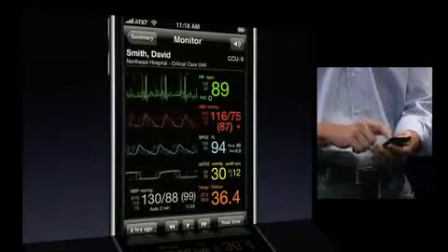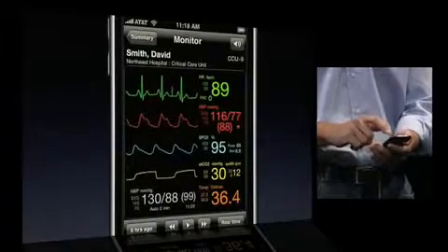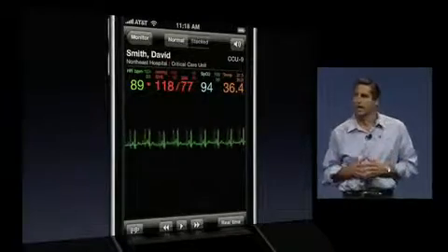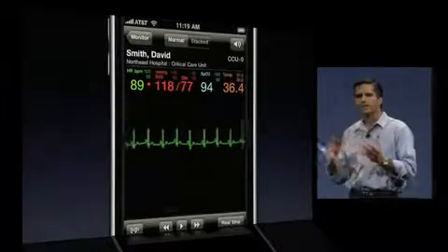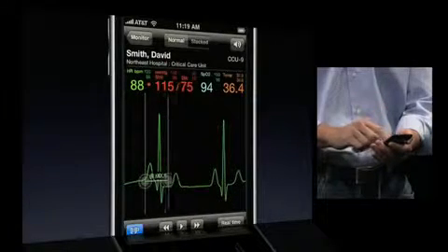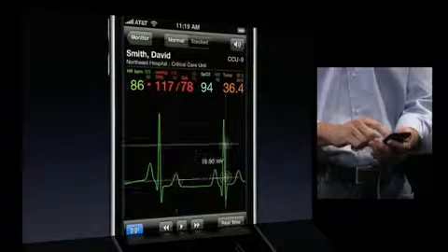to an event that may have occurred in the past, and then if I'm interested in that cardiac waveform, I can double tap on the tracing. I can enable pinch zoom. I can scroll back over time to look for abnormalities, and then if I see something of interest, I can zoom in, and I can enable touch calipers. This is really great. I can use the calipers to measure the distance between a cardiac event or perhaps the size of a waveform.